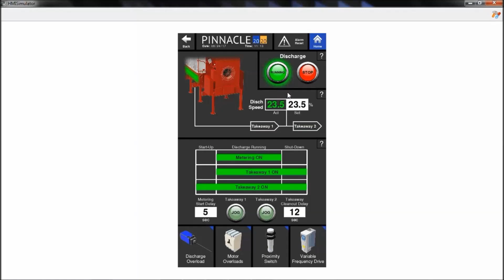So on your initial startup, you should keep the discharge speed at a low speed until you figure out where you're at. That's not a bad idea. You're saying on day one to start that discharge speed slow, at least until you can figure out that everything's turning on as intended. And do make use of those jog buttons. When you hit one of those jog buttons, you'll be able to see exactly what equipment is tied to that signal. So it's a good way to verify if you've plugged in the equipment to the right customer input. You can push jog number 1 or jog number 2, and you should hear that equipment click on immediately. That'll help you in determining if you've wired it up correctly.